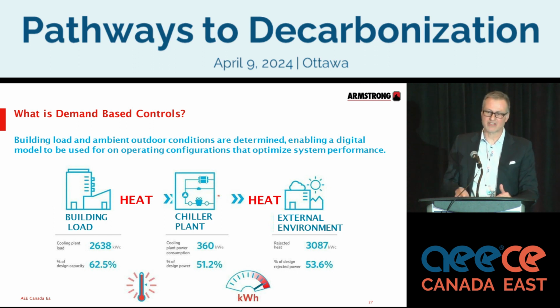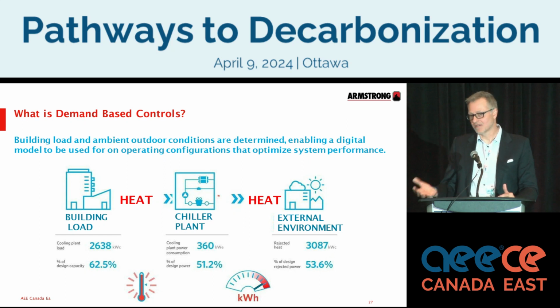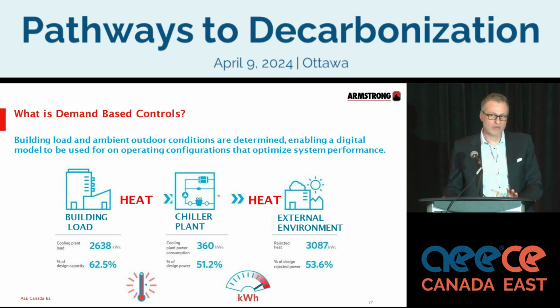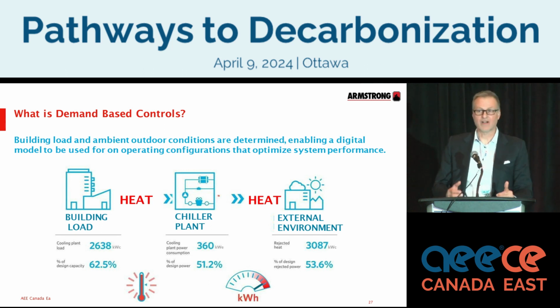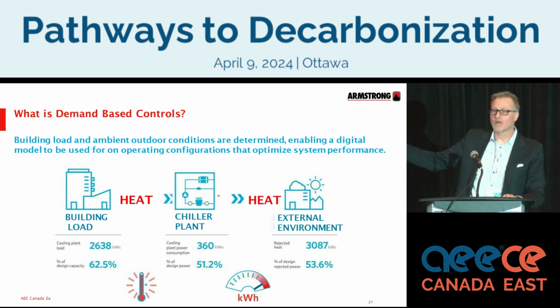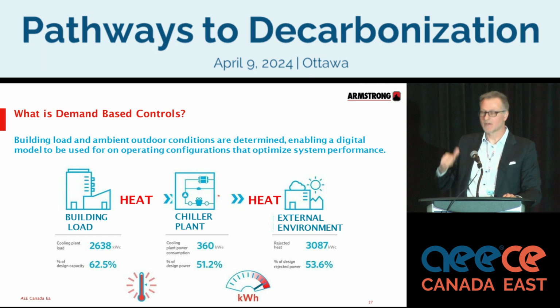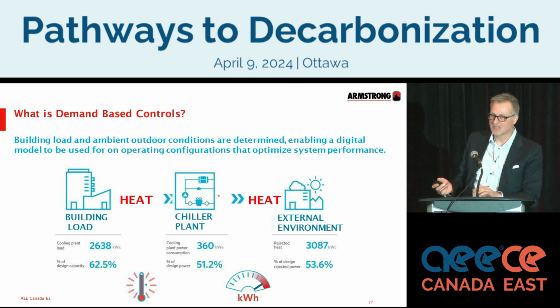So if you understand that and you understand the mentality of typical controls, now take a step back. We always want to have the lowest possible temperature entering the condenser side of the chiller because we want to lower the lift. A typical controls contractor will set that at 65 or 75 degrees depending on what the chiller manufacturer specifies. But if it's 95 degrees outside, you're never going to get to 75 degrees. Your fans don't know that. Your fans are going to run at 100%. They can run 120%, but you are not going to move any more thermal energy other than what that approach is designed for. And that's one of the keys. So now, if we know what the building load is, we know the ambient outdoor conditions, especially on the condenser side, we know where to operate the equipment and the speeds that they can operate at.